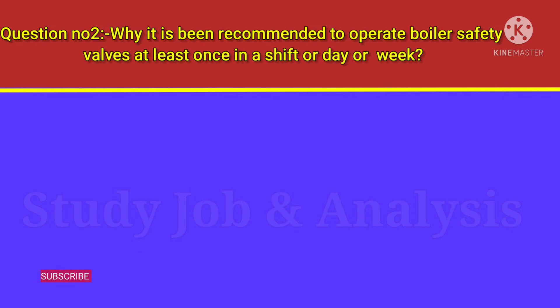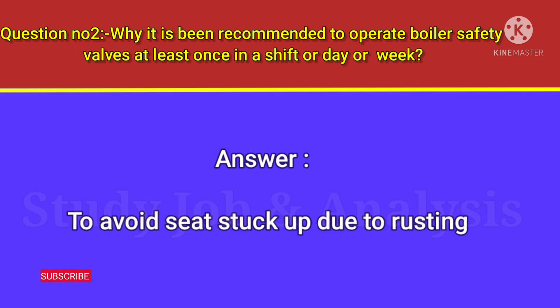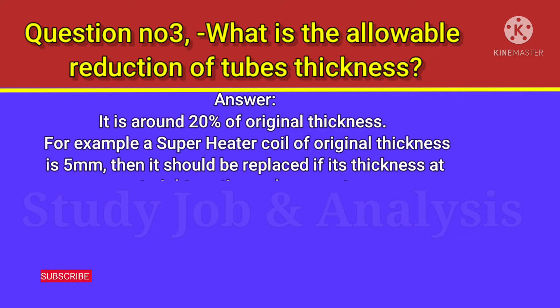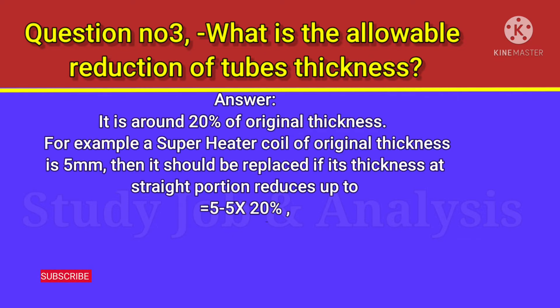Answer: To avoid the seat getting stuck up due to rusting. Question number three: what is the allowable reduction of tube thickness? Answer: It is around 20 percent of the original thickness.